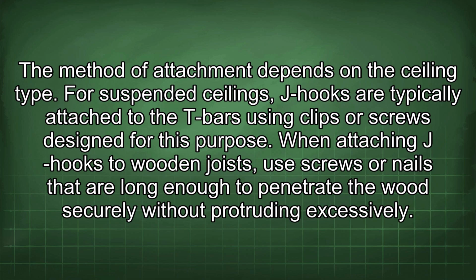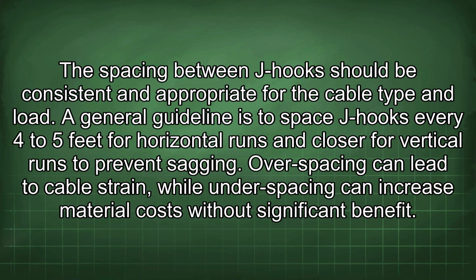When attaching J-hooks to wooden joists, use screws or nails that are long enough to penetrate the wood securely without protruding excessively. The spacing between J-hooks should be consistent and appropriate for the cable type and load. A general guideline is to space J-hooks every 4 to 5 feet for horizontal runs and closer for vertical runs to prevent sagging.